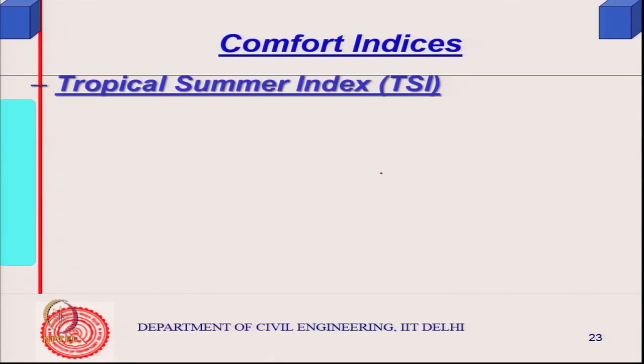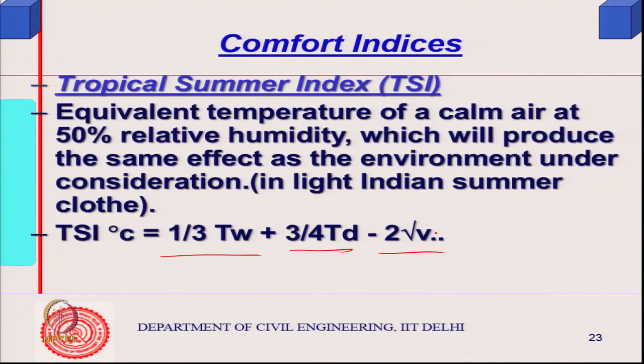This is the tropical summer index we looked at in the last class. The formula associated with this is approximately one-third wet bulb temperature plus three-fourths dry bulb temperature, minus two times the square root of V. This is a slightly more empirical, slightly more elaborate equation, but good enough for our purpose. This is the equivalent temperature of calm air at 50 percent relative humidity which will produce the same effect as the environment under consideration.